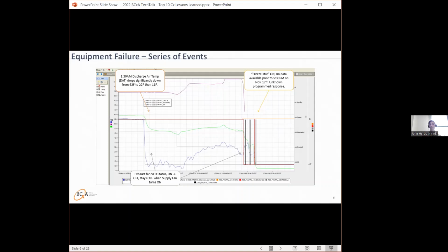Besides cursing a lot, we started pulling up how did this happen - we started doing failure analysis immediately. This is the trend that I pulled up to share with the team for the meeting. We had a meeting the next day, and we showed the discharge air temp dropped significantly down, and we're like, why did we all of a sudden lose a safe operating condition to a non-safe condition and a frozen coil?